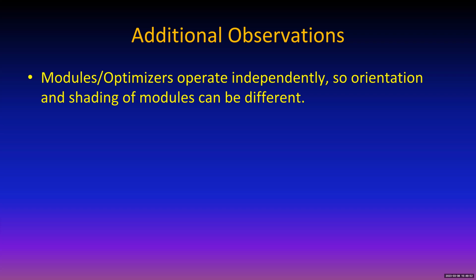Now the modules and the optimizers, they operate independently, so orientation and shading are not a big issue. In one string, you can have some modules pointing south, some pointing east, some pointing west if you want to, or some shaded and some not shaded. And the modules and the optimizers, they do their thing to optimize the output from each module and keep the inverter happy by adjusting the voltage to what the inverter would like it to be.